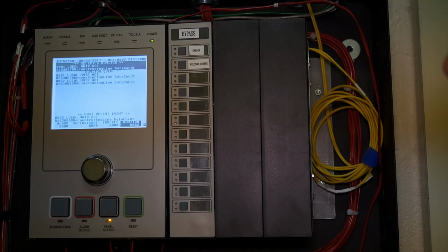Anytime you restart the panel like that, there's a loop controller on this panel and the panel up there. They're going to reconstruct their map on the loop controller. That's what you're going to get every time. It's just saying that it's going out and re-looking at its devices and reconstructing and making sure that everything still matches up with what it's supposed to be. So that's normal. It'll do that every time you restart the panel. Maybe a minute or two and it'll clear up and you'll be back to normal.